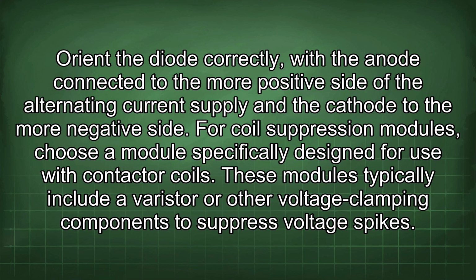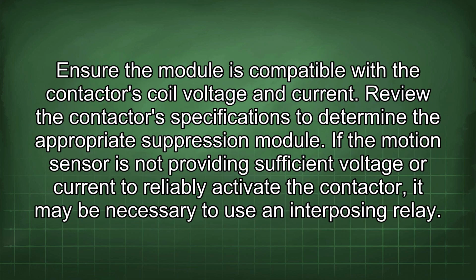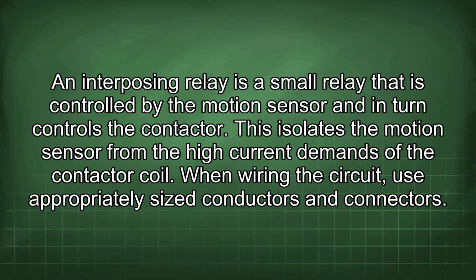For coil suppression modules, choose a module specifically designed for use with contactor coils. These modules typically include a varistor or other voltage clamping components to suppress voltage spikes. Ensure the module is compatible with the contactor's coil voltage and current. Review the contactor's specifications to determine the appropriate suppression module. If the motion sensor is not providing sufficient voltage or current to reliably activate the contactor, it may be necessary to use an interposing relay. An interposing relay is a small relay that is controlled by the motion sensor and in turn controls the contactor. This isolates the motion sensor from the high current demands of the contactor coil.